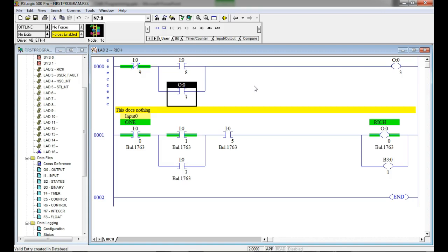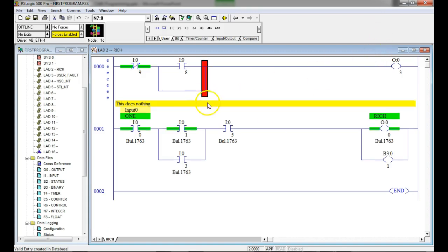It's all computers. So if it's not a real coil, if it's a software coil, which is what we have here. By the way, I'm not going to assign it to an output. I just thought of that. Now we're going to use this as a start-stop station for everything inside our PLC program. I don't want to sacrifice one of my output coils for doing nothing but preventing this guy from coming in, right? You understand? So what I'm going to do is I'm going to come up here and I'm going to assign this to what we call an internal coil.